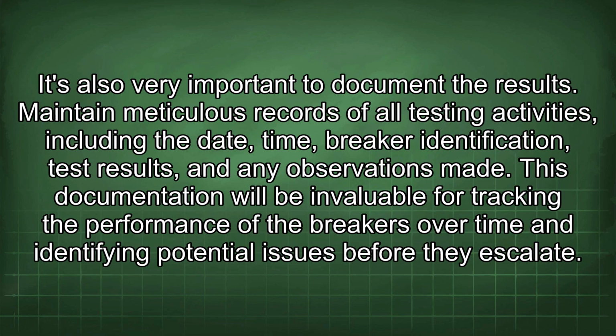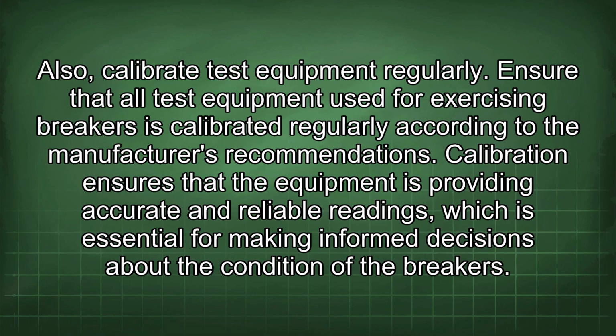It's also very important to document the results. Maintain meticulous records of all testing activities, including the date, time, breaker identification, test results, and any observations made. This documentation will be invaluable for tracking the performance of the breakers over time and identifying potential issues before they escalate. Also, calibrate test equipment regularly.